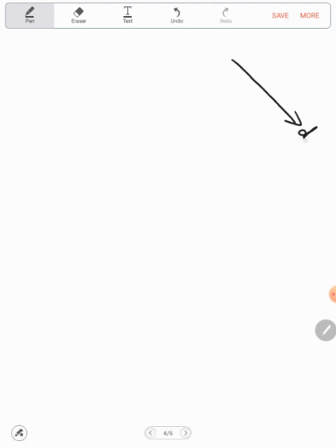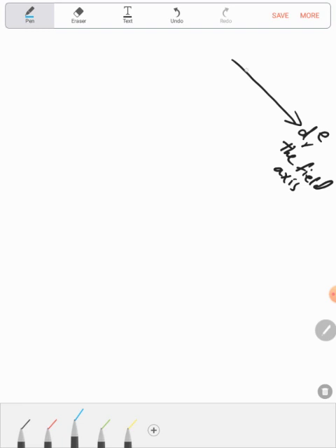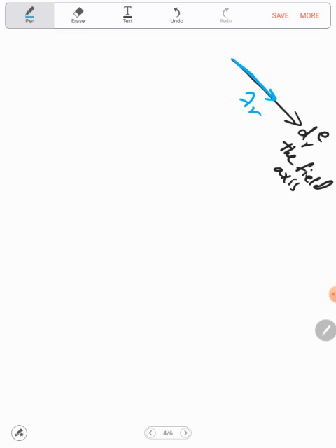So let's repeat here. If we can manage to align our reference frame, the d-axis of the reference frame, which in general we call the field axis, in the direction of the rotor flux, lambda r, we get lambda qre equal to 0, and lambda dre equal to lambda r, which by definition, or simply by assumption, is constant.